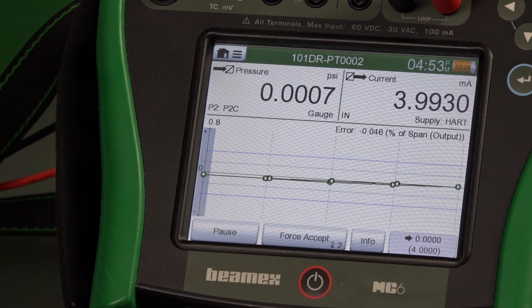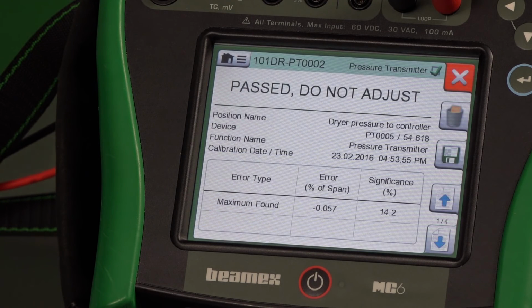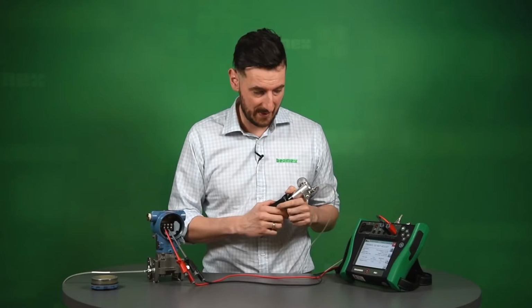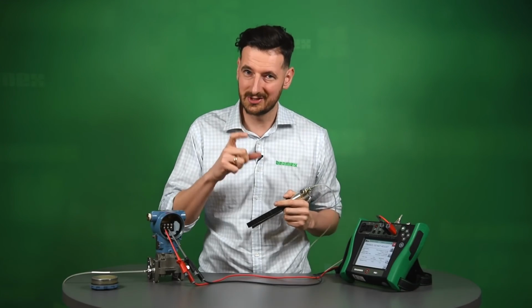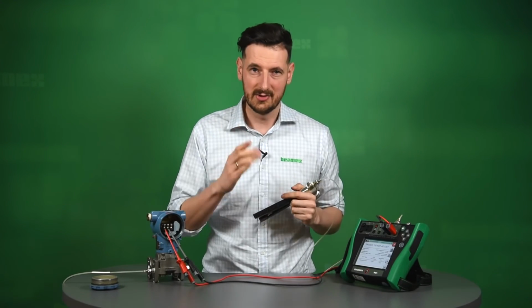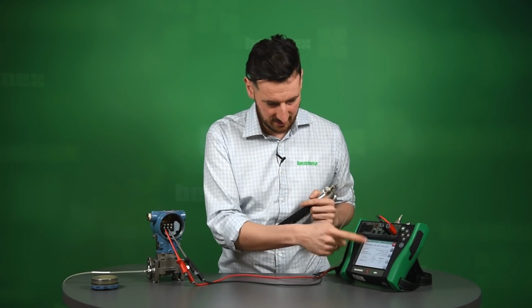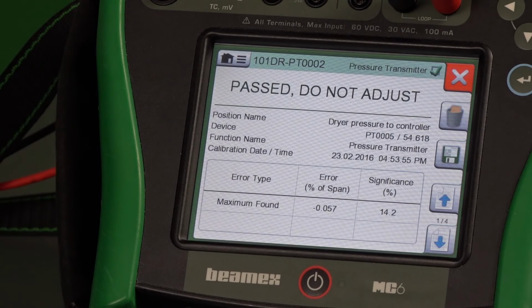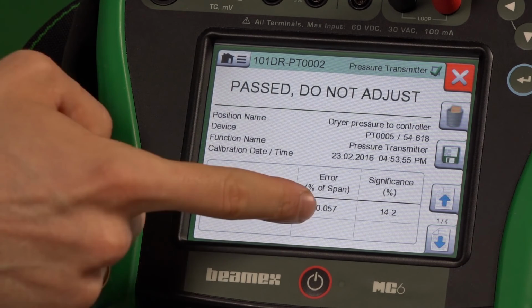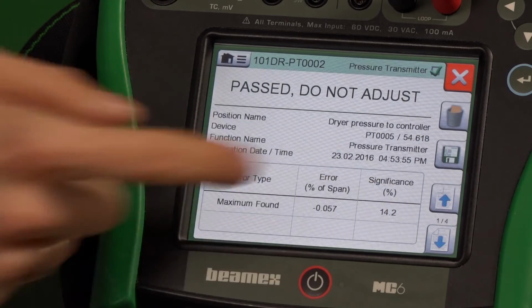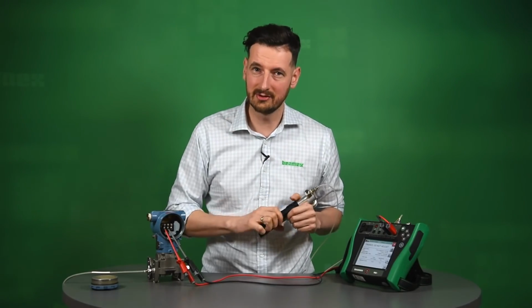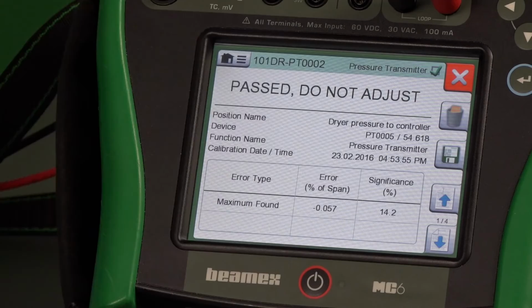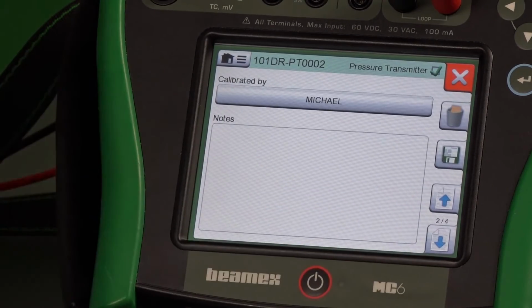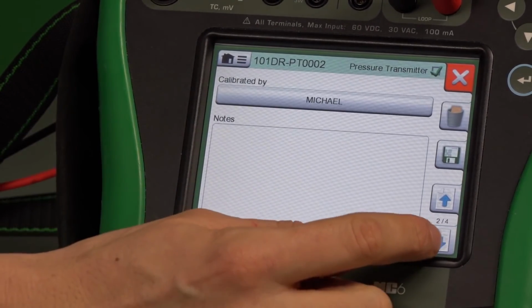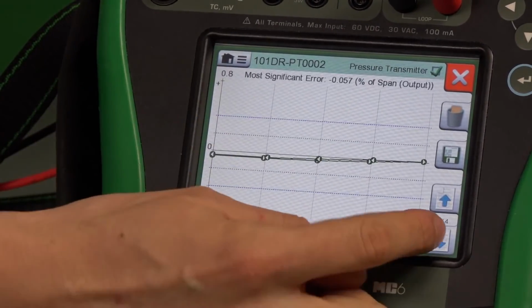So you can actually see that we are well within tolerance. It says here passed, do not adjust. You remember again those conditions that we set previously. You can actually see that they are in place now and they're working. Look at that again, 14.2% significant error, tiny error. This value may not be that much, but that value does. So just make sure you understand what that significant value is. So very low significance of that error. So that's good.